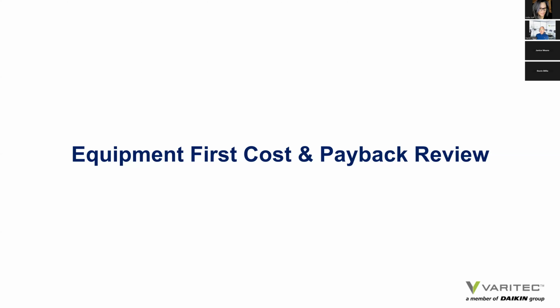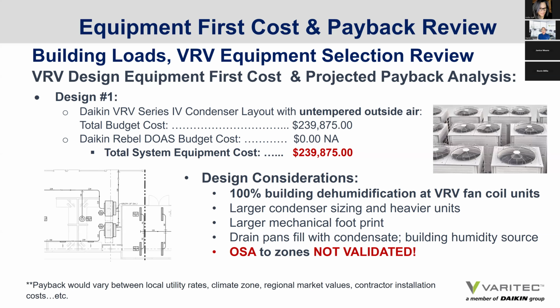Well, what about equipment first costs and payback? We've got to make this system affordable. Well, I'll just show you the numbers and you make that decision for yourself. So, we went ahead and priced the systems and we looked at the untempered outside air design scenario, and we find that the overall equipment cost for the variable refrigerant system where the total sensible and latent load was handled at the fan coil, we had an equipment cost of $239,875. That does not include installation, that does not include copper piping or whatever. This is just the variable refrigerant manufacturer's equipment.